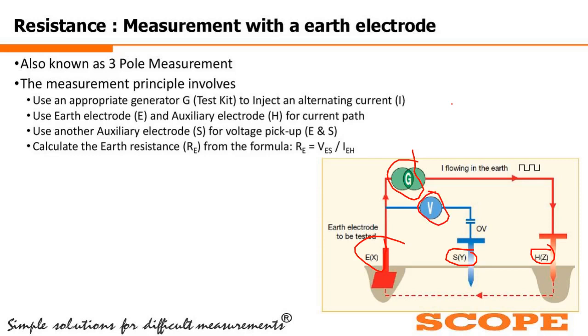So we can use an appropriate generator or the test kit to inject a current which will be flowing through the earth in this path as shown, and in between these two points I will be taking the voltage drop. So we are going to use the earth electrode E and auxiliary electrode H for the current path. We can use another auxiliary electrode S for voltage pickup. So in between E and S I will be taking the voltage.